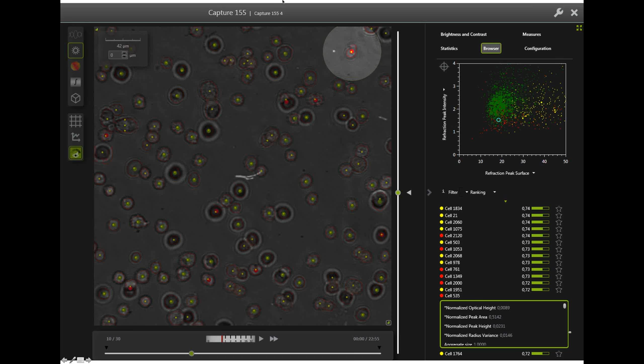The difference between a classical flow cytometer and the charts created with our system is that when you click on a dot, you get the corresponding image of the cell. The system also automatically draws the growth curves of the bioreactor. So you see we have many more measurements. We have a measurement point almost every 30 minutes. Every 30 minutes we take a sequence of 25 holograms, and that allows us to compute in a very accurate way the growth curve of the bioreactor.